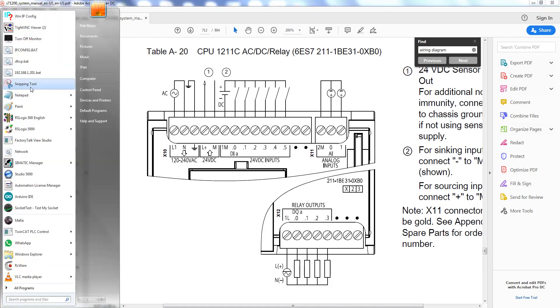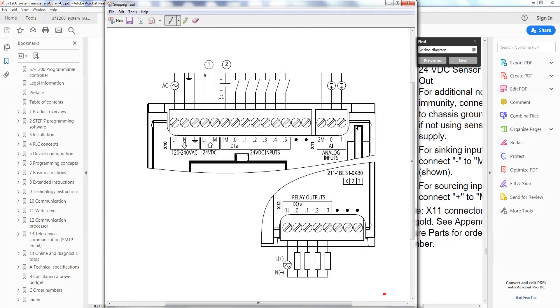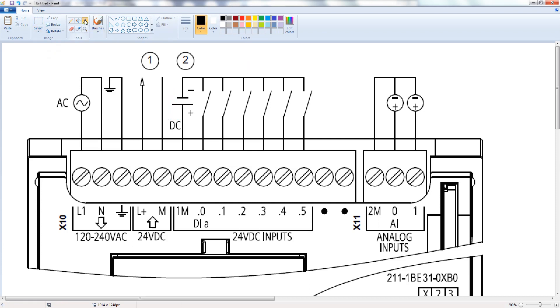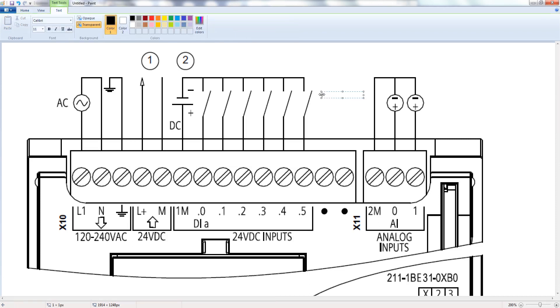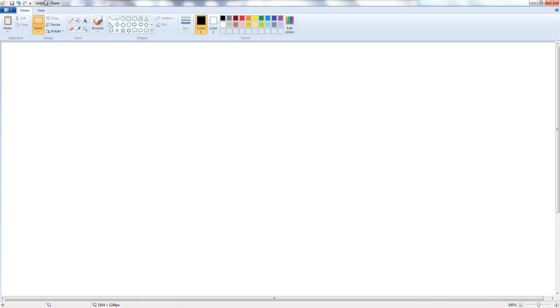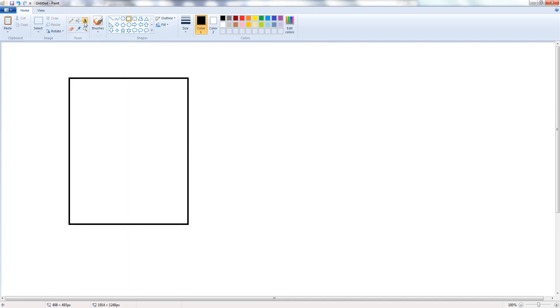If you want to use NPN sensors, you have to change the wiring diagram. The NPN sensors are switching the negative. The negative goes to the sensor, and if the sensor turns on it's sinking — so it's called a sinking sensor. The positive is permanently wired to the input.